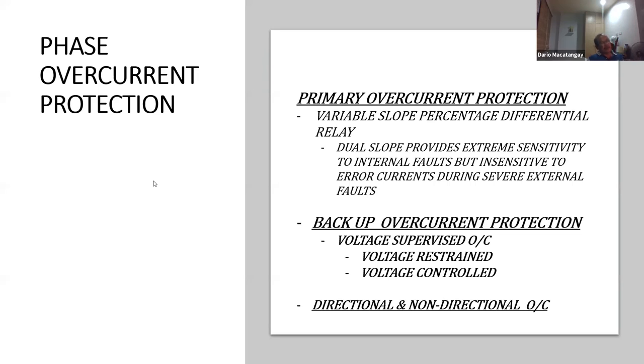Then in that case, if you don't have something that can synthesize between that small value and the high value, it's kind of difficult to set. The other problem here is that the load current of the generator is very high. Just imagine a generator rated at 2000 amps. If the sustained fault, because of that high XD, is only 1,800 amps, you need to set the relay at 1,800. But you cannot trip the relay at that set point, because you need a load of 2,000 amps.